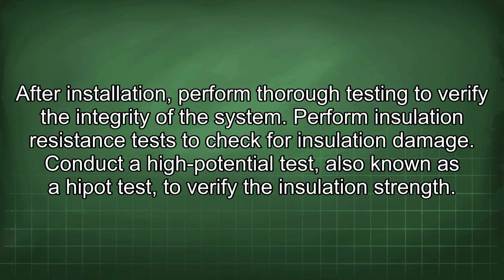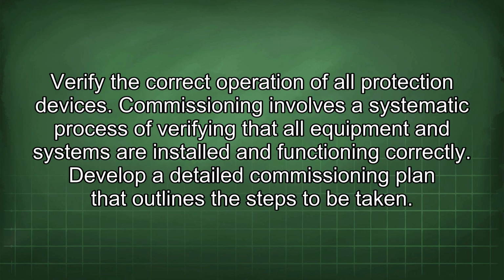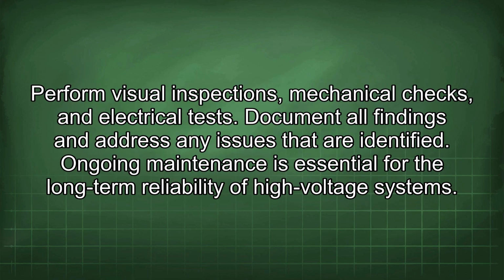Conduct a high potential test, also known as a HIPOT test, to verify the insulation strength. Verify the correct operation of all protection devices. Commissioning involves a systematic process of verifying that all equipment and systems are installed and functioning correctly. Develop a detailed commissioning plan that outlines the steps to be taken. Perform visual inspections, mechanical checks, and electrical tests. Document all findings and address any issues that are identified.